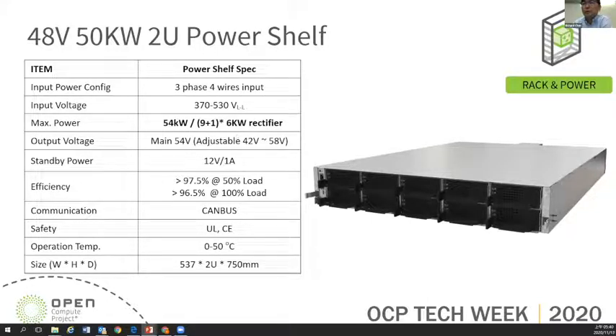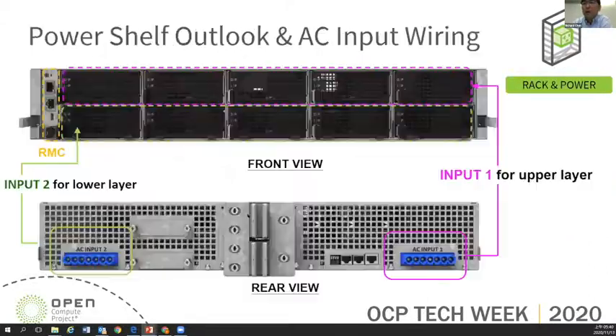Same with the 48 volt output. And also, we have a standby 12 volt that provides power to the measurement. Then we use a CAN bus for internal communication. So to check the rear side and the front side of this design, we reserve space for 10 pieces of power supply, and also the spacing for a rack monitor device.